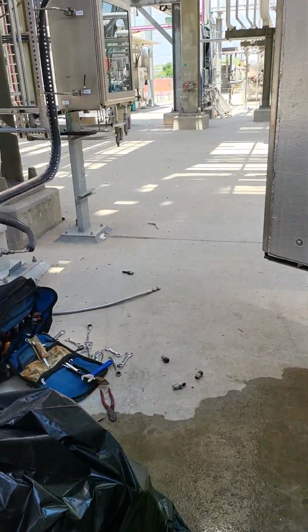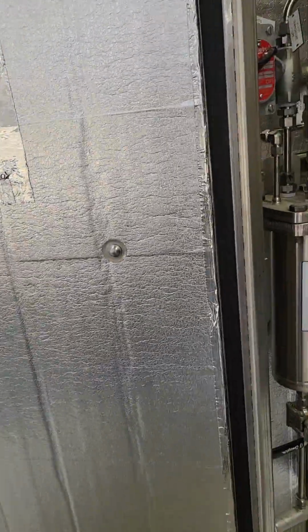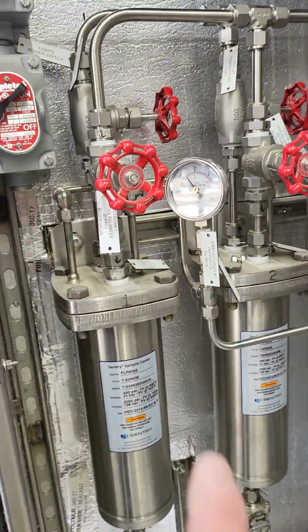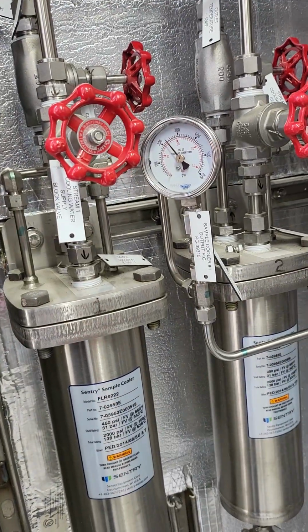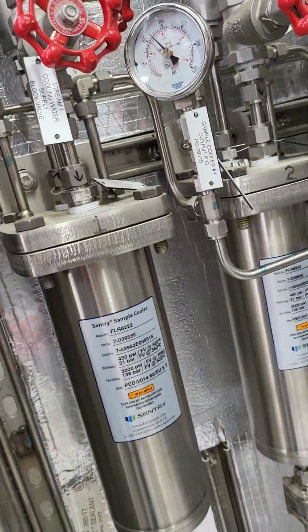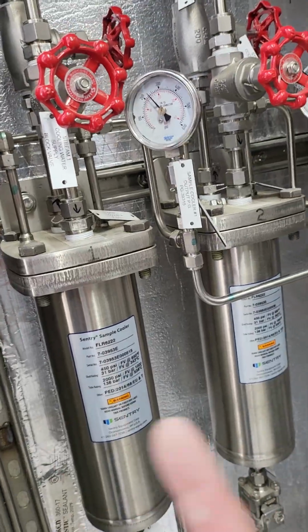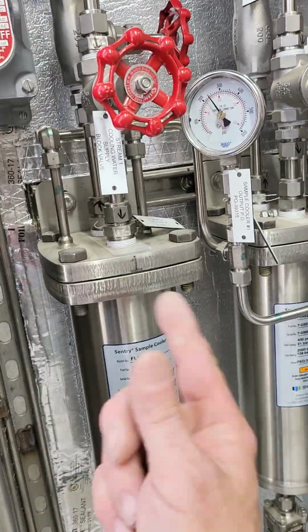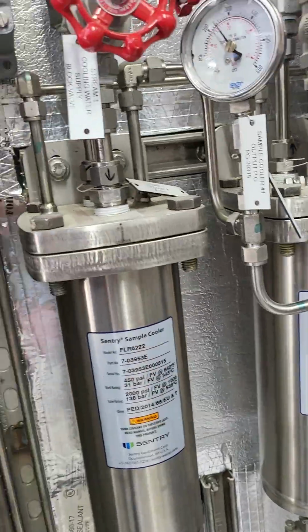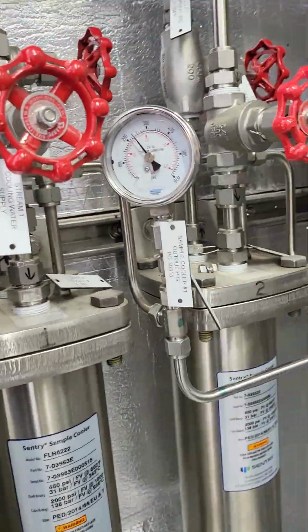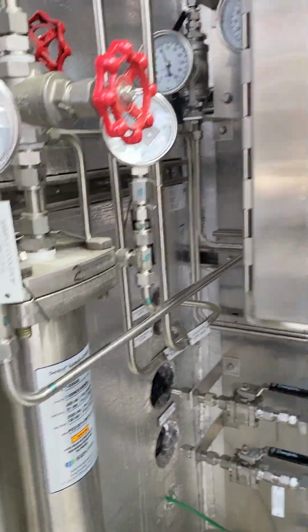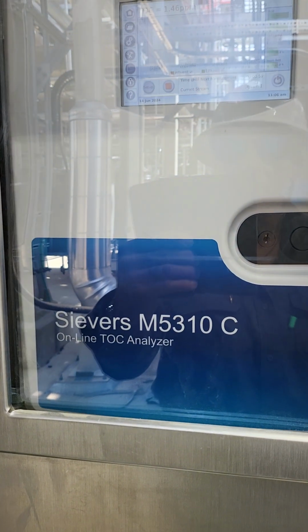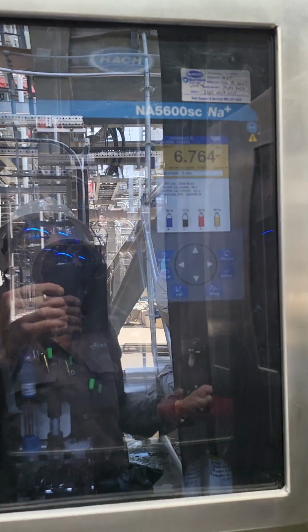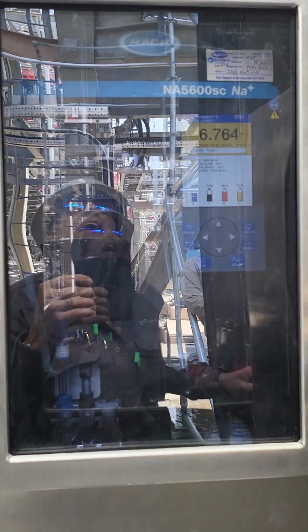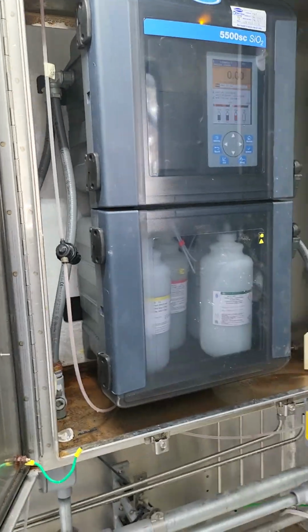Oh, son of a bitch. This is cooling tower water. These are actually heat exchangers. So you bring our sample in. The sample's going to go through these, with the cooling tower water circulating around the sample, which is inside a coiled tube. And that coil of tubing is bringing our sample up and out. After you cool it down, you send it over here to the total organic carbon, then we're going to have sodium, and then we're going to have silica.